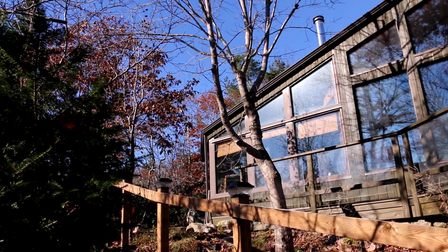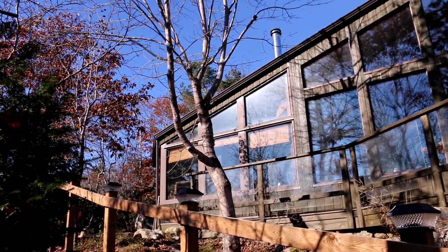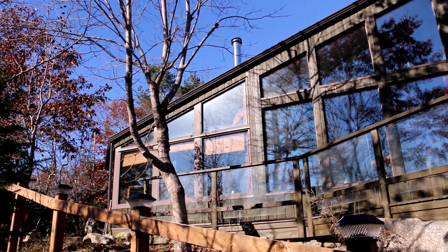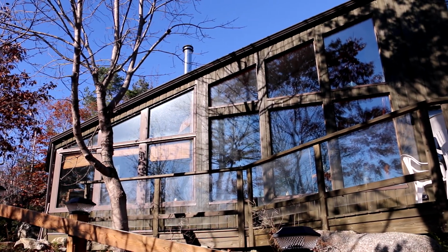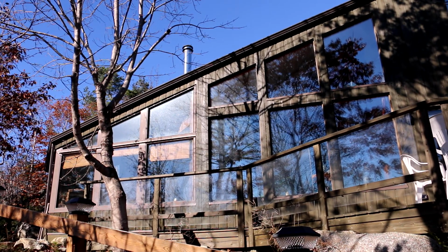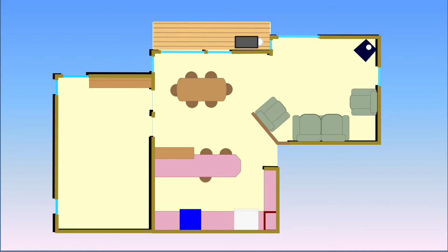If you have a lot of glass, you're going to have to go beyond the building code's airflow requirements. Air has a low heat capacity. You need to move a lot of air to move a lot of heat. As a rule of thumb, our experience has shown that moving the whole air mass in a room or the home in about 30 to 40 minutes does the job.